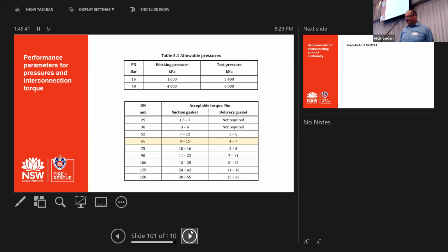And there's a table in 5.3, which is the interconnection torques. Yeah, it's shown up, so in orange, I can't really see it on my screen. 65 mil, which is what goes on the 500 valves and boosters. So it's 9 to 15 Newton meters of torque. Now, Fire Rescue New South Wales may potentially be purchasing some torque wrenches, and we'll actually measure these when we do our tests on buildings.